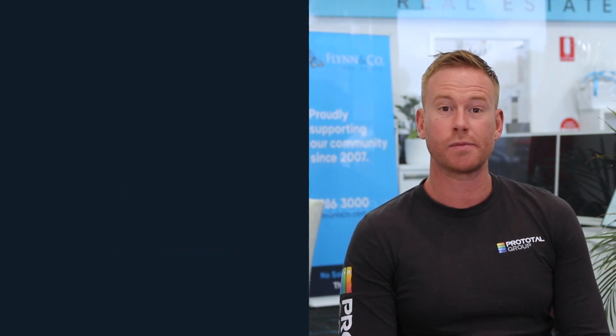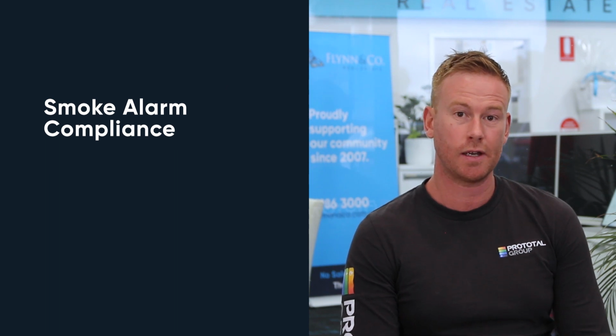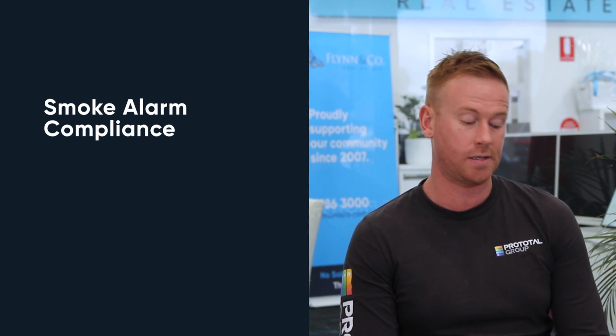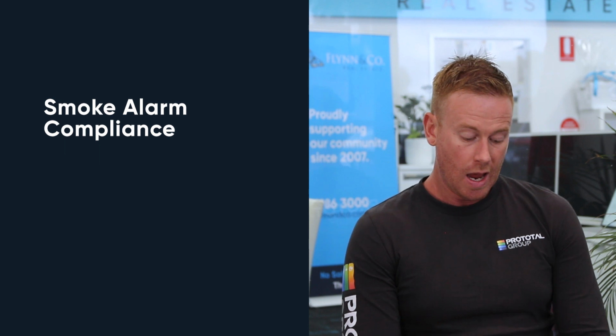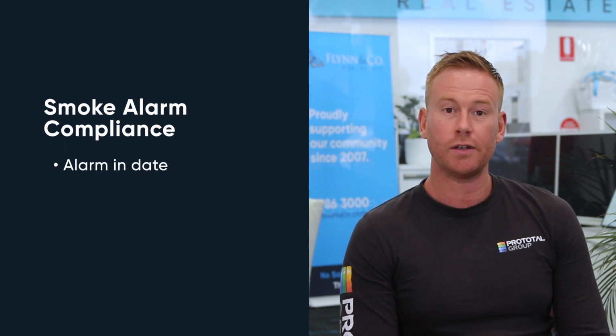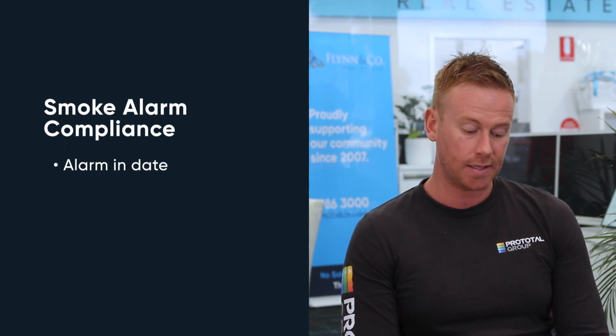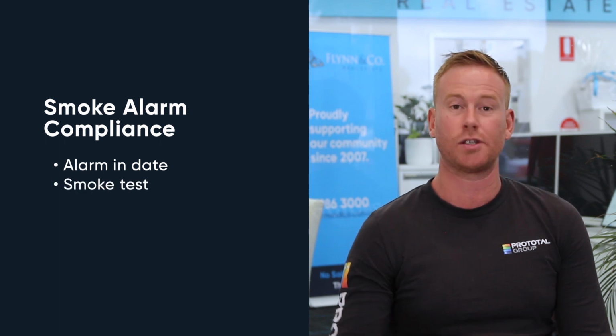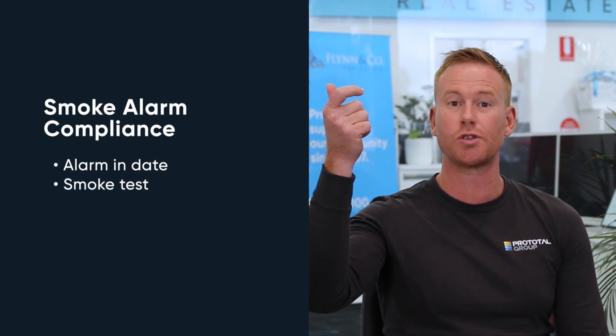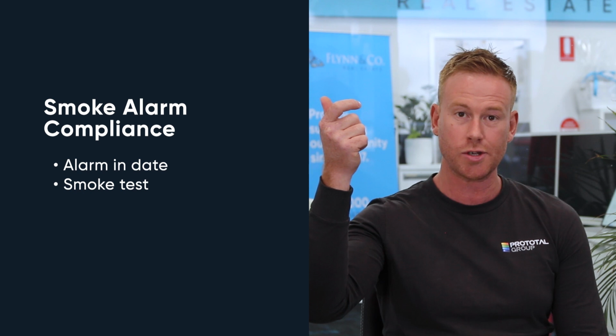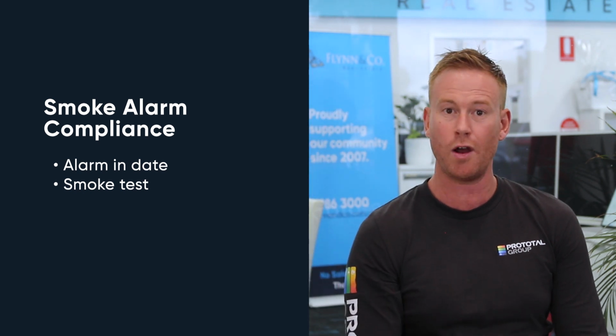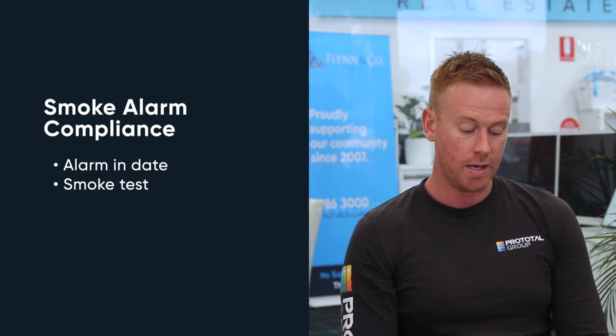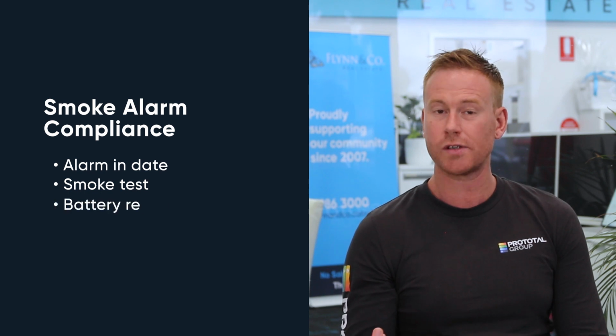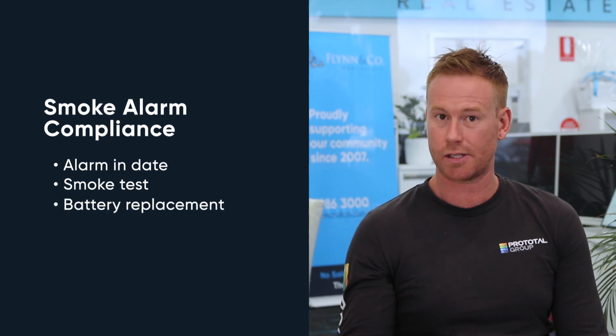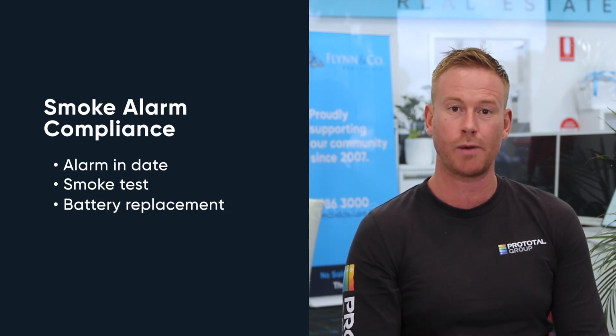Our smoke alarm safety compliance inspections are tested in accordance with AS 3786, and we test if the alarm's in date. We actually do a physical smoke test to make sure that your alarm is operational in the event of smoke or fire. We replace the battery, obviously, so it's captured in the next 12-month round of safety inspection testing.